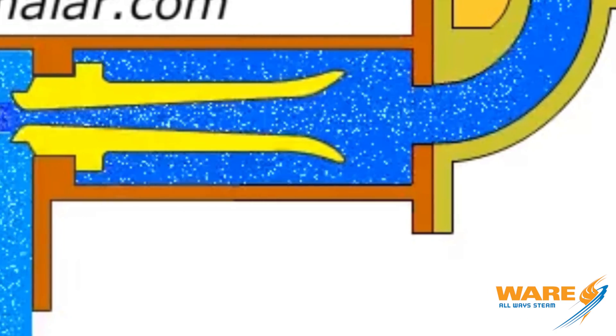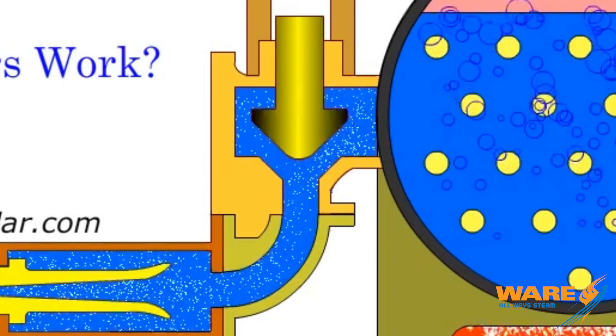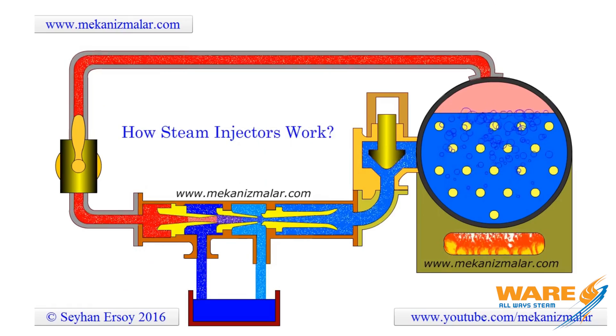Now you have steam flowing through the nozzle at a great rate of speed. It's going to get to the other end, and as it comes out the pressure is going to increase because of the area increase, but it's going to slow down a little bit. That's okay because it has enough pressure to overcome the pressure that's in the boiler — and that's how they feed it. The great thing about this is there are no moving parts and this is a perpetual cycle. As long as they feed steam to that nozzle it's going to create a vacuum, entrain the water, and take it all the way to the boiler.